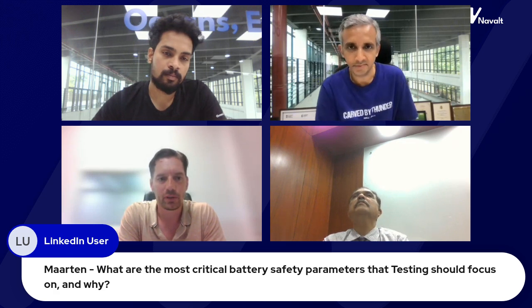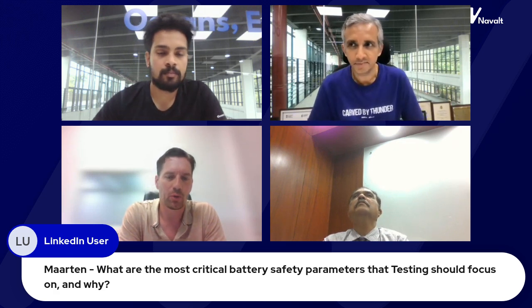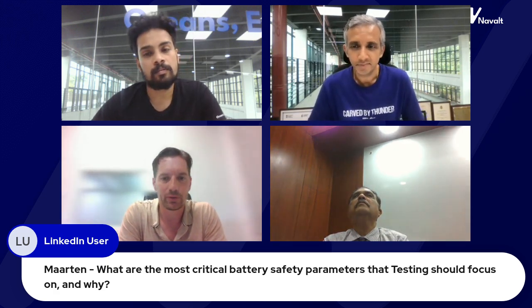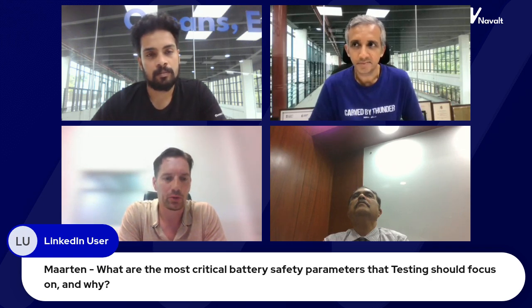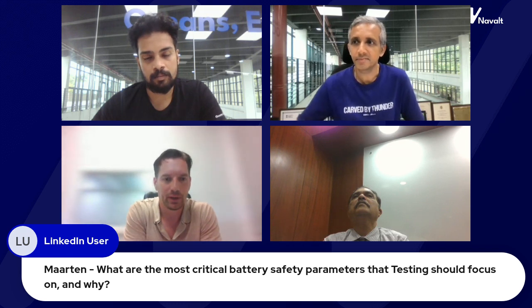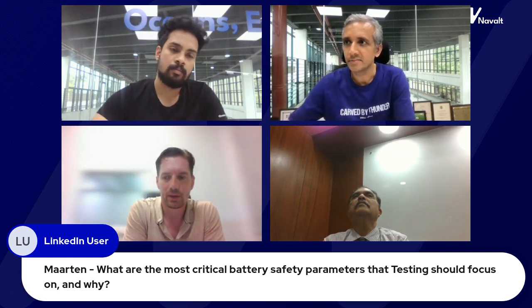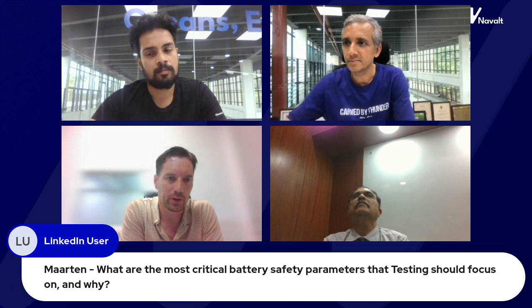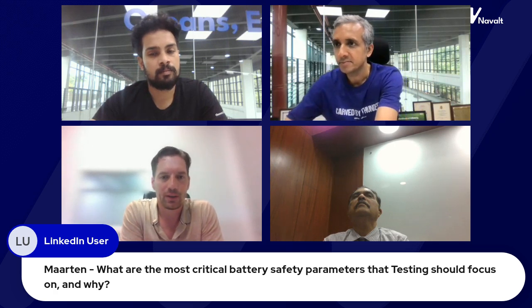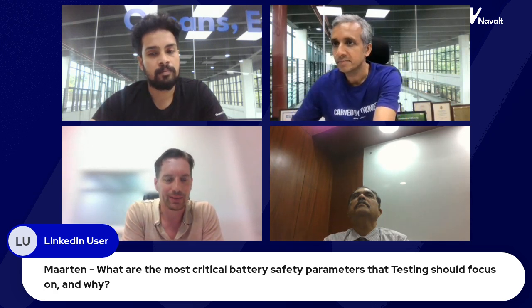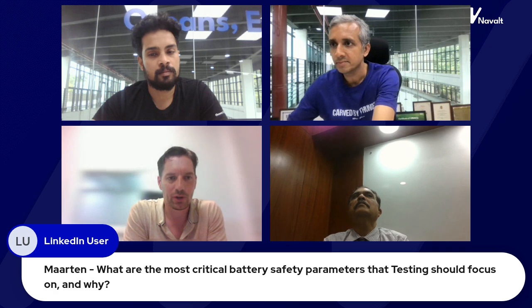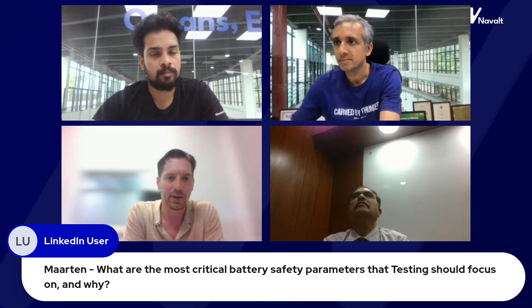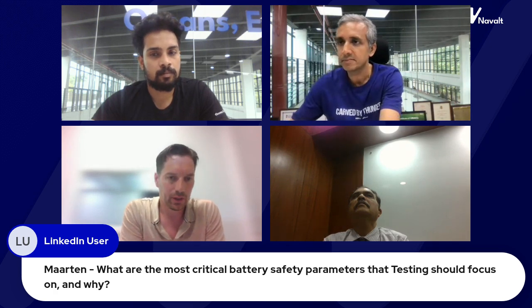At a system level it becomes even more complex because we have contactors, circuit breakers, fuses, and manual service disconnects. You have to take that into account. You have to be careful that at the moment something goes wrong and there's a very high short circuit current running through your system, your contactors are not trying to act as circuit breakers. You have to be sure circuit breakers are doing their job properly and being used in the right way.